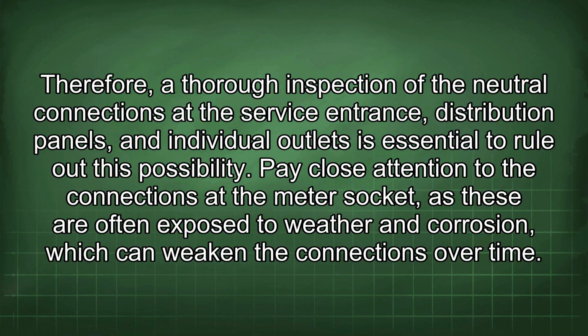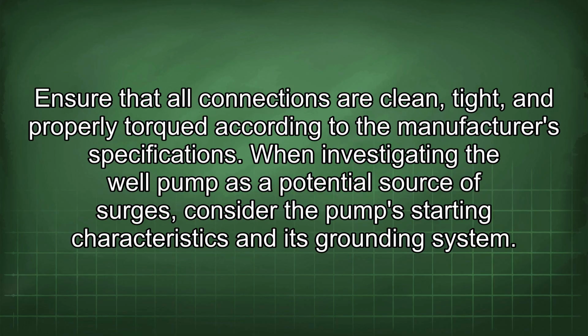Pay close attention to the connections of the meter socket, as these are often exposed to weather and corrosion, which can weaken the connections over time. Ensure that all connections are clean, tight, and properly torqued according to the manufacturer's specifications.